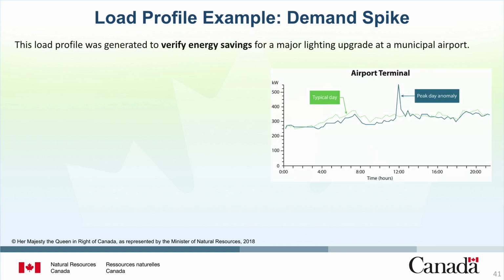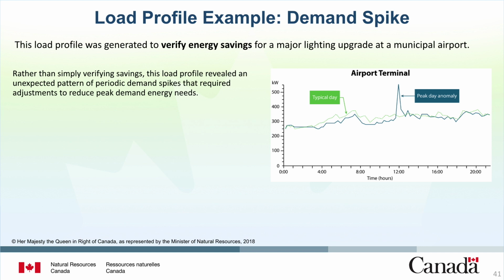Next, let's identify a spike in demand from a load profile using an example. This load profile was generated to verify energy savings for a major lighting upgrade at a municipal airport. Rather than simply verifying savings, this load profile revealed an unexpected pattern of periodic demand spikes that required adjustments to reduce peak demand energy needs.